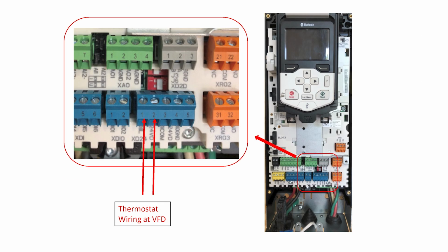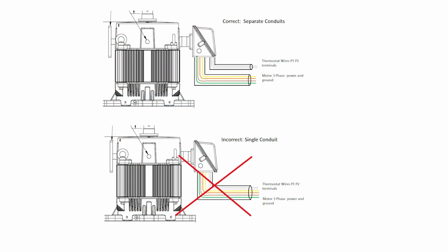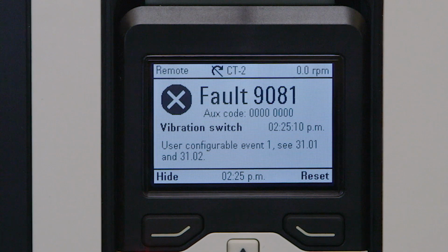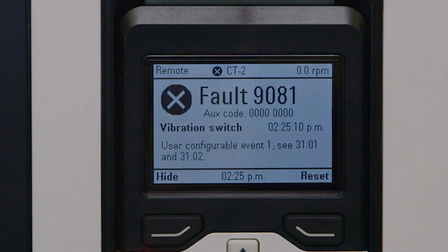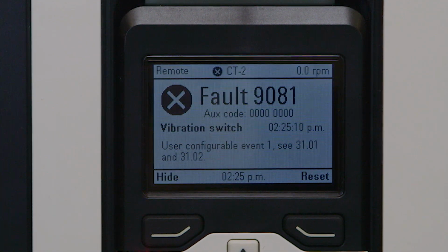Once the motor cools down, VFD terminal XD2D-1, labeled as DIIL, and terminal XD2D-2, labeled as +24VD, will close and the alarm will clear automatically. Ensure that these wires are correctly attached. Note, if this alarm occurs intermittently, confirm the thermostat wires are not in the same conduit as the motor power wires. If the vibration switch at the tower opens, the display will show a vibration switch fault message and a red LED light will appear.